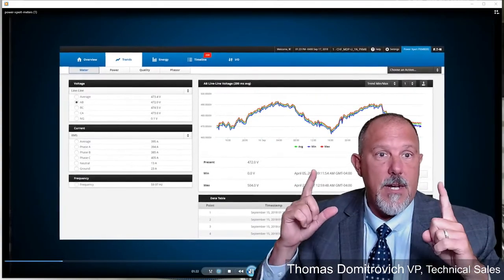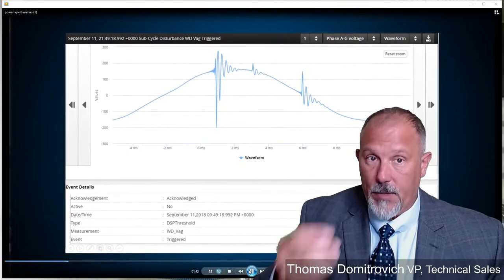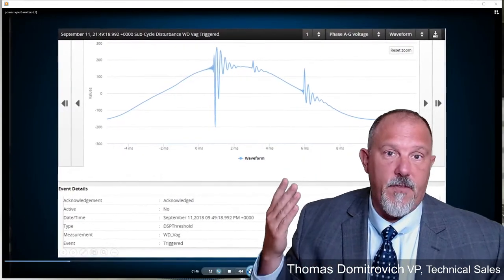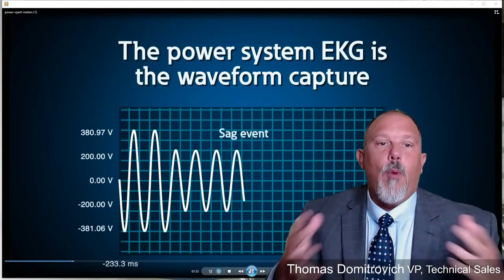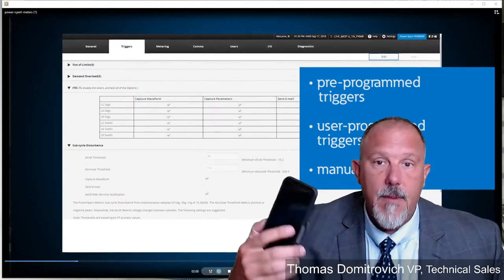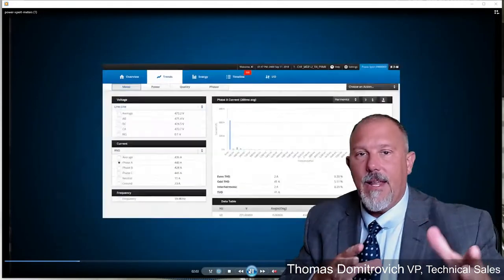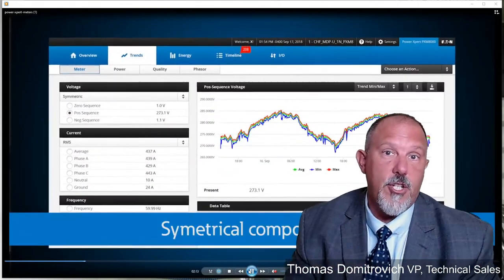And you'll notice that this graphic is an HMI, a human machine interface on a computer. It's showing waveform data from what could be a relay, and you'll notice that's a subtransient type of event. That's a ring wave, probably from capacitor switching or some switching type of event. These waveforms, how do I get waveforms from a device back to a computer or to my cell phone? How do I get that information back to a computer that might not even be in that location? Maybe back to a display on the big gray box so I can view that information either on the assembly, or maybe it's outside the room where that assembly is. I have a display like this that I can have all of that information.